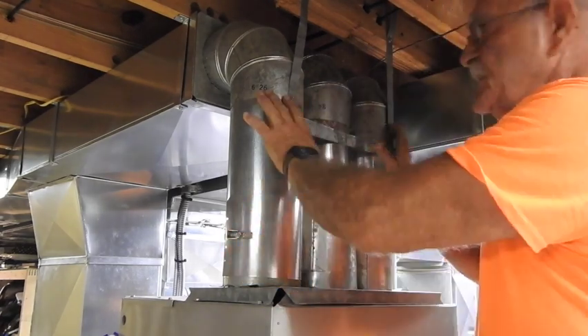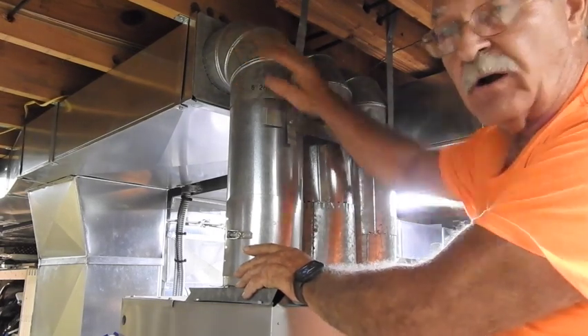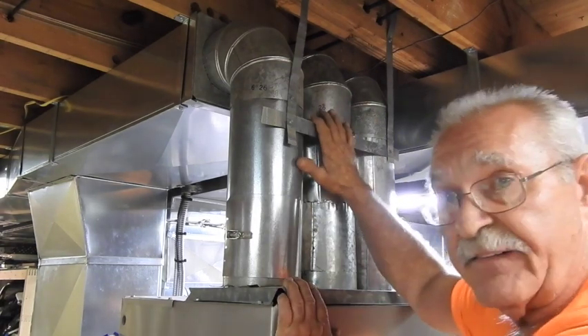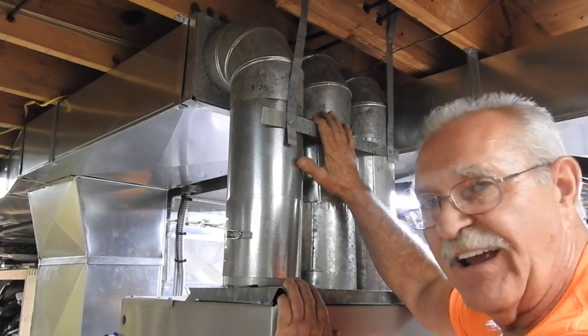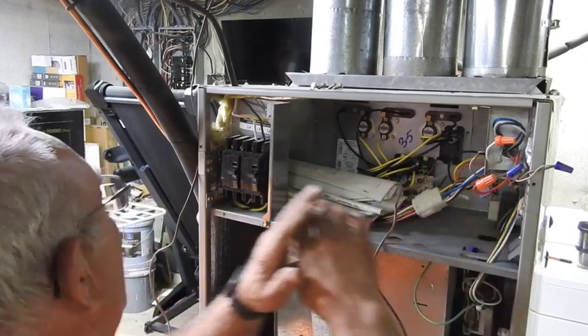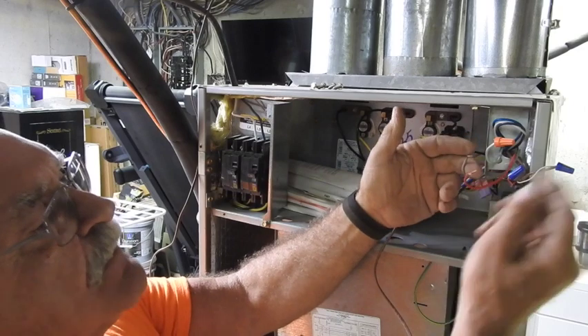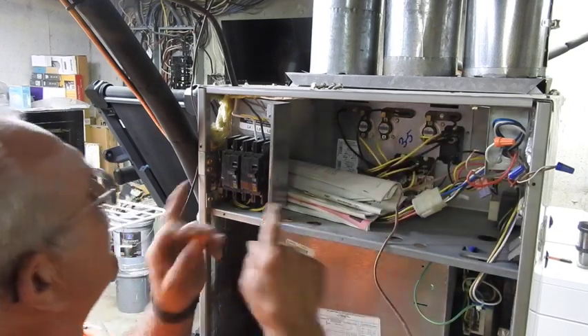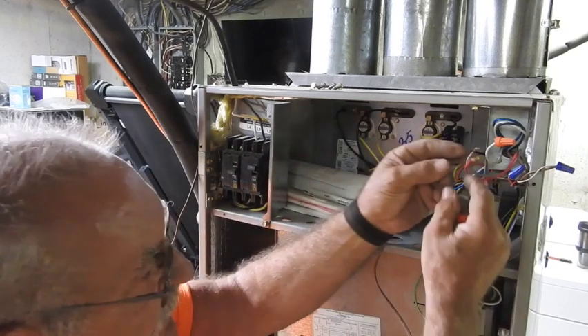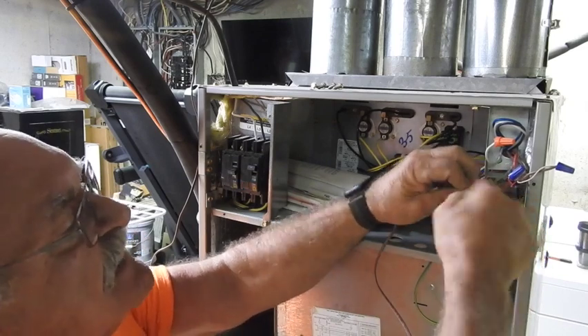Pay no attention to all this — this is entirely temporary, just like I've stressed. What we've got is three six-inch supply runs going into the return air trunk, and we're going to go ahead and start up the blower right now to see how noisy it is and see if it's going to do what we want it to do. On the old existing furnace — the one that has the air conditioning coil in it — I'm going to pull out the thermostat wires that will go to the thermostat for power and also come back from the thermostat to energize the cooling fan relay. We've got power temporarily from the other furnace, so when I connect these two wires here it should be like turning the thermostat blower control to the on position.